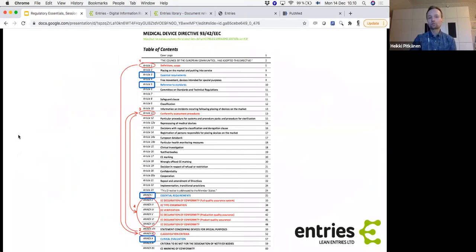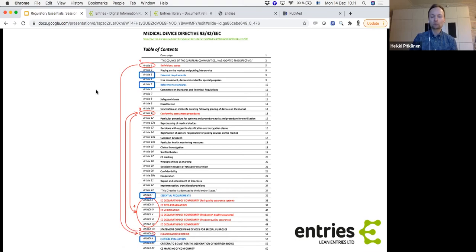Reminder, this is the old or former medical device directive, and it's its table of contents. And here in blue are the parts of the regulation or the directive that consider the product. They talk about the essential requirements. That would be the same as what are now called the general safety and performance requirements in the MDR and IVDR. And that's first described in one of the articles, and later the essential requirements here in Annex 1 would be the heart. Then there is a reference to standards also in those articles, and clinical evaluation mentioned in Annex 10, and the risk management resides within Annex 1.